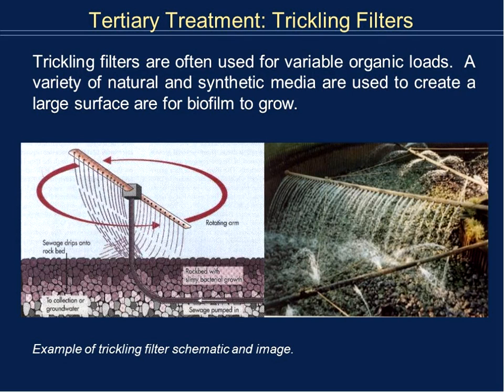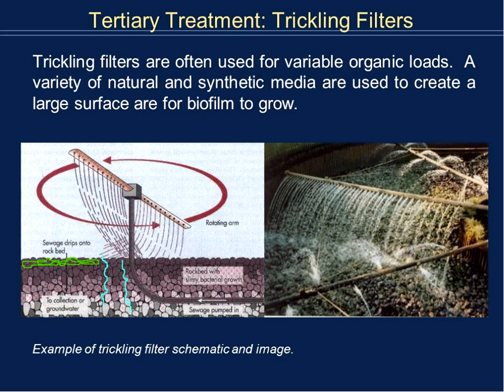We're going to move on to trickling filters in particular, just to do an example and go through some properties. If you think of a sprinkler you'd use on your lawn, flip it upside down — instead of sprinkling up, it sprinkles down directly. You would see a granular media — maybe gravel or a synthetic plastic. As the water trickles through the gravel media, any organic material starts to be consumed by a biofilm that develops on top. This looks like algae. The algae will consume any organic material as the water trickles down — that's where we get the name trickling media filter.